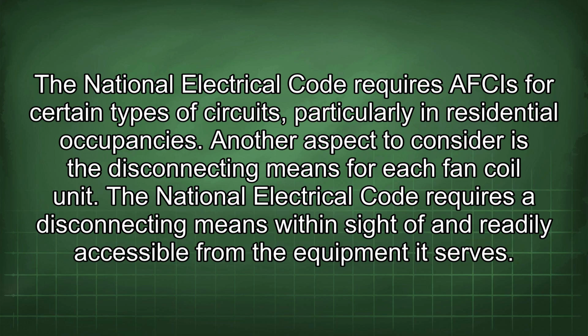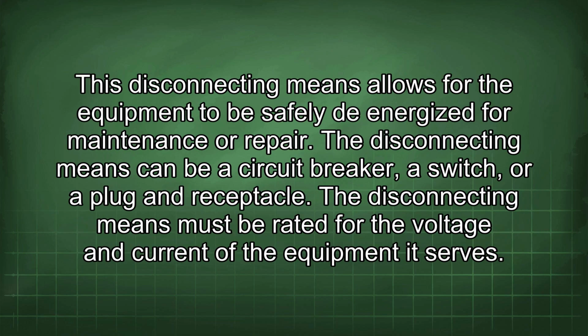Another aspect to consider is the disconnecting means for each fan coil unit. The National Electrical Code requires a disconnecting means within sight of and readily accessible from the equipment it serves. This disconnecting means allows for the equipment to be safely de-energized for maintenance or repair. The disconnecting means can be a circuit breaker, a switch, or a plug and receptacle. The disconnecting means must be rated for the voltage and current of the equipment it serves.